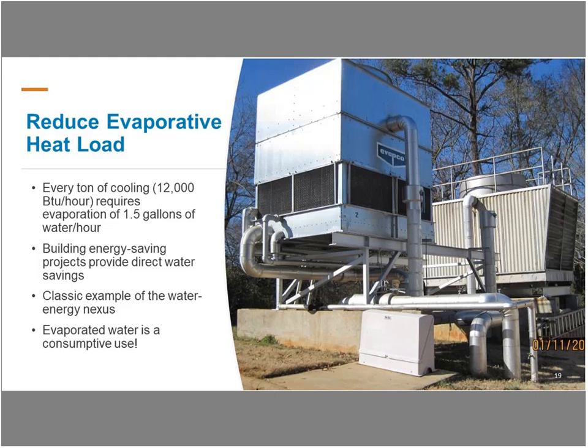So aspects of your facility that may impact your evaporative load include building design and envelope, HVAC design and equipment selection, lighting and plug loads, occupancy, operating characteristics, and maintenance practices. So lighting retrofits, system efficiency upgrades, and other efficiency projects that you implement that have energy savings likely will also have a commensurate water savings if you use a cooling tower.